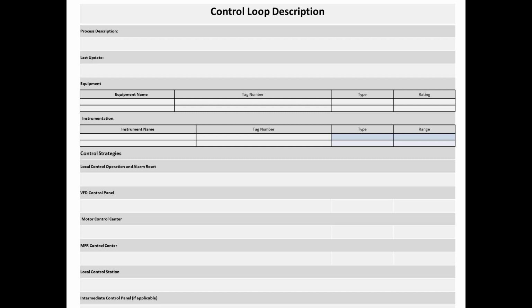The VFD control panel: many pieces of equipment don't have a VFD, so under that you just put not applicable. However, on some pieces of equipment, for example a pump, you may say that in order for the VFD control panel to operate, the local control switch at the local control station needs to be in remote. This basically gives you the instructions on how to operate something at the local control panel.